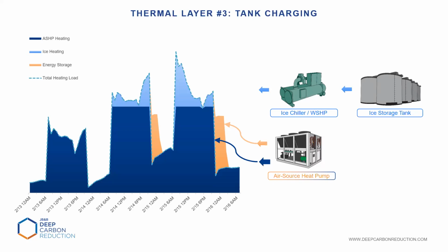How we deploy this ice heating system: we first start with the air source heat pump that provides the heating you need up to some midway point, usually whatever capacity of heat pump you can fit on your roof. You operate the heat pumps up to their capacity, and then to fill the remaining bucket of heat you need, you deploy the ice heating solution. You deploy the ice chiller, which is also a water source heat pump, to fill that remaining load.